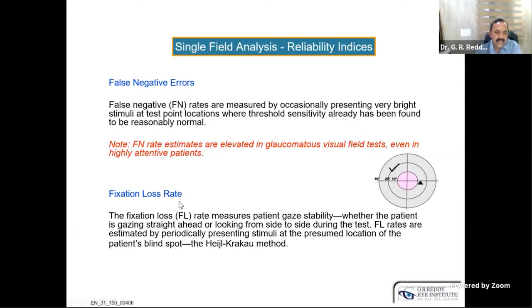Coming to fixation loss, that means how he is fixing during the entire test. There are two methods, the blind spot method and gaze tracking. Gaze tracking is the patent of Humphrey. In the blind spot method, whenever you fix the central fixation or small diamond or a big diamond, the machine locates the blind spot. During the test, the light falls on the blind spot and the patient should not respond. If he is responding, it means he is moving the eye.